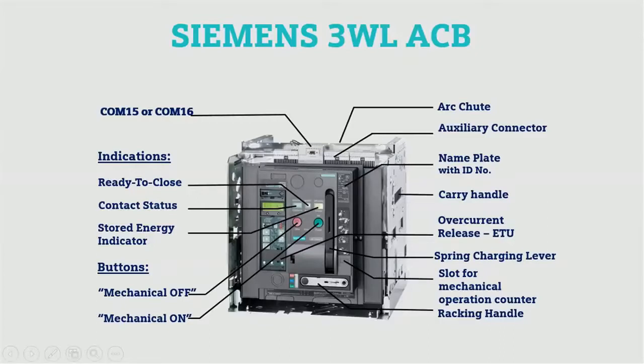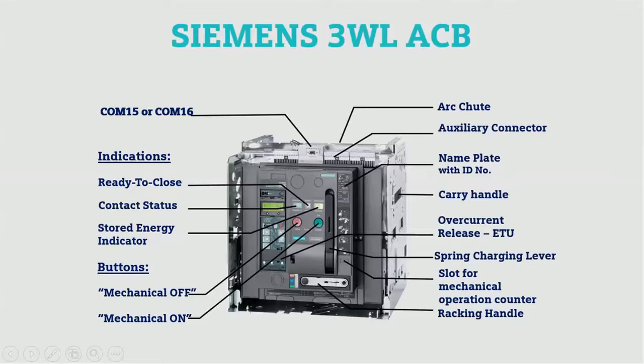Starting from the nameplate, you will get detailed information on current and voltage ratings and technical data. There are two mechanical buttons — on and off — to open or close the contacts. There is also a spring charging lever; by using this lever you can charge the spring, and from the window you can see whether the spring is charged or not. The contact status — whether the contact is closed or open — is also indicated here, along with an ACB indication for ready to close.